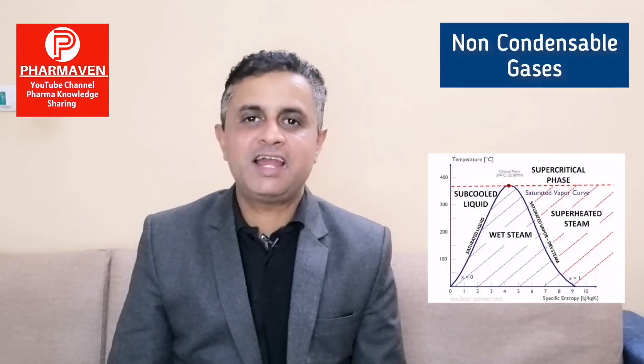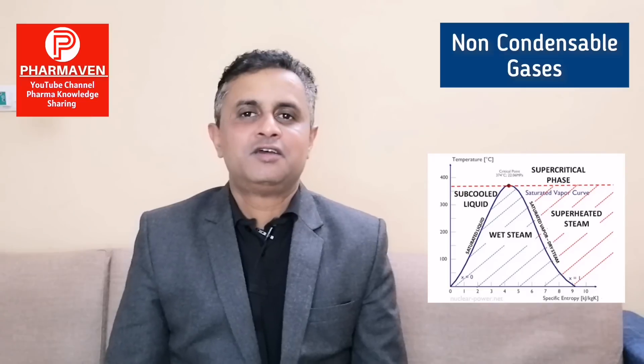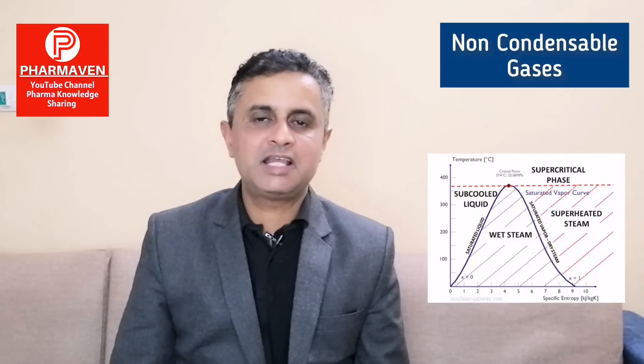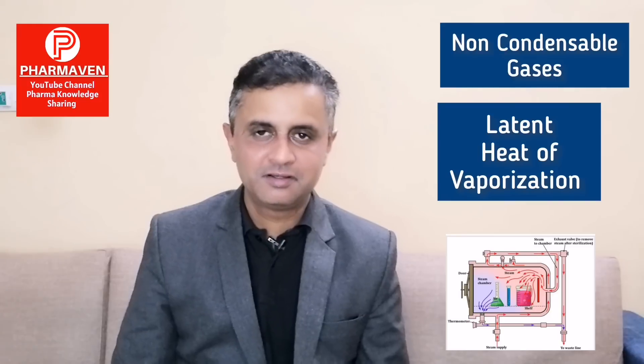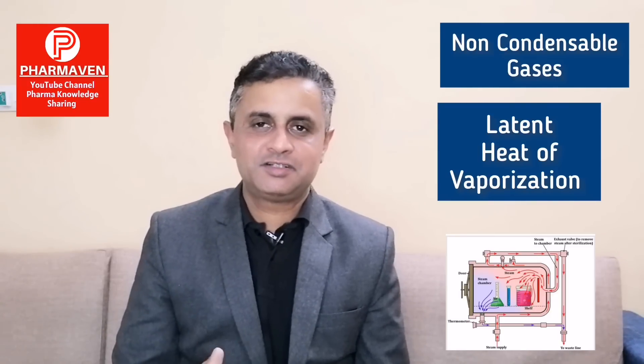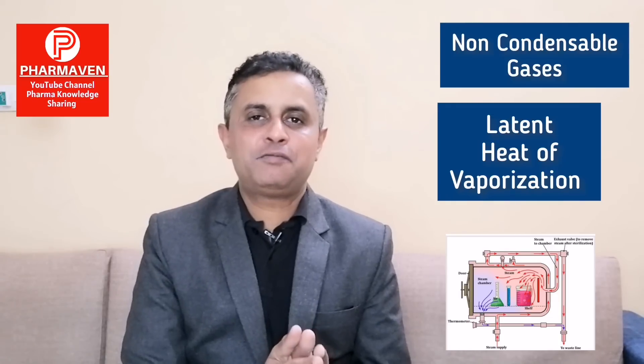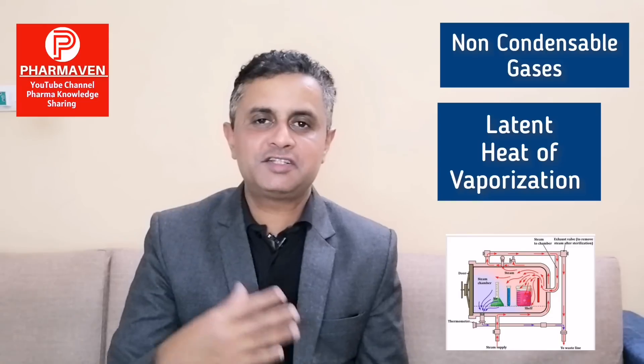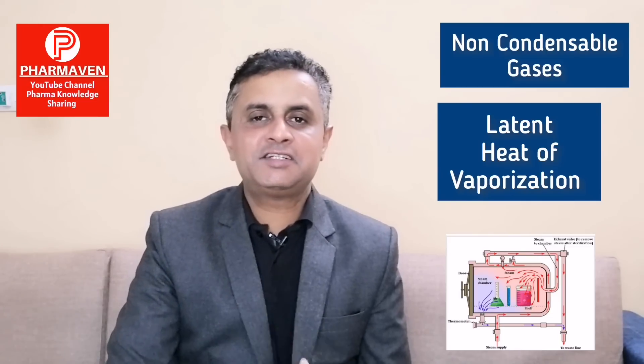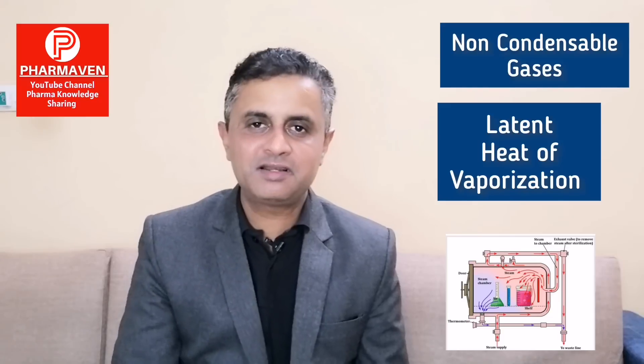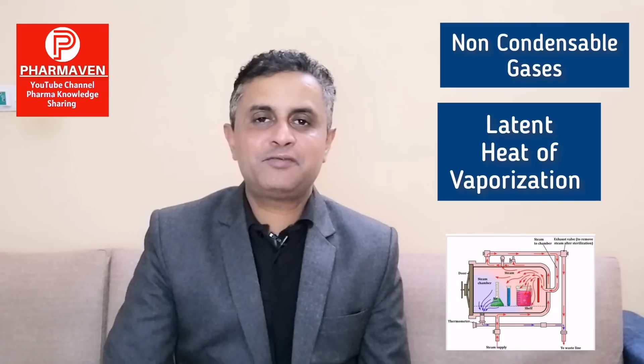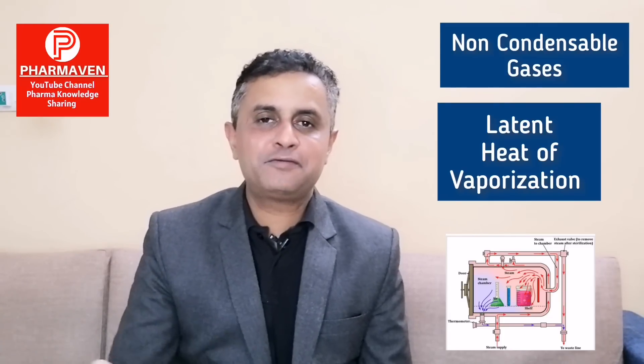Let's start with non-condensable gases. Before that we must understand how steam acts and how steam kills microorganisms. When we heat water it converts to steam. The amount of heat required to convert water into steam is called latent heat of vaporization. When steam condenses in the chamber onto the load, that latent heat of vaporization — the energy used to convert water to steam — is transferred from steam to the load items, increasing the load temperature.